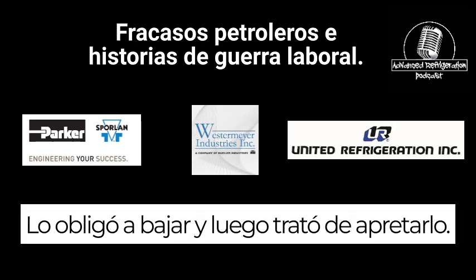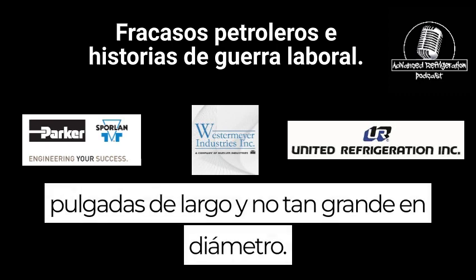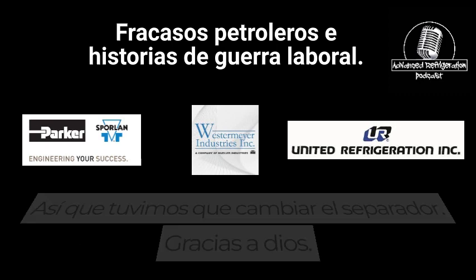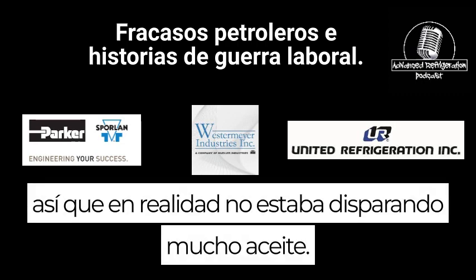He forced it down and then tried to tighten it down. And then what happened was he ended up breaking it off. Well, at that point, the thing's probably 14 inches long and not that big in diameter. So there's no way that you're going to set a welder down there to fix it. So we had to change the separator. Thank goodness it was a scroll rack that had very constant flow. So it wasn't really shooting a lot of oil through.